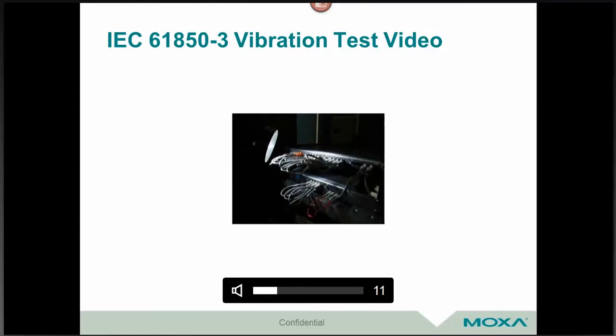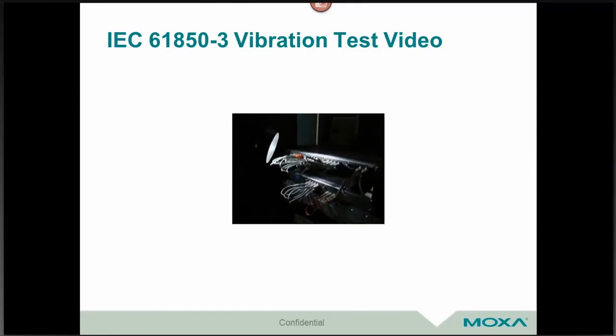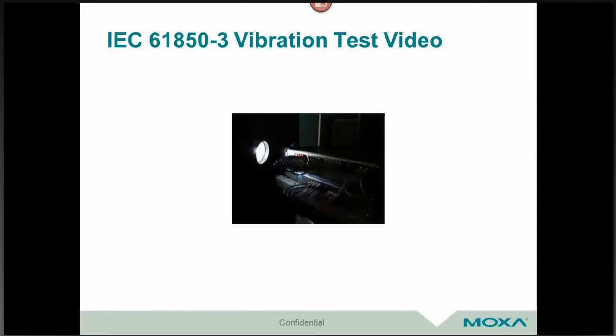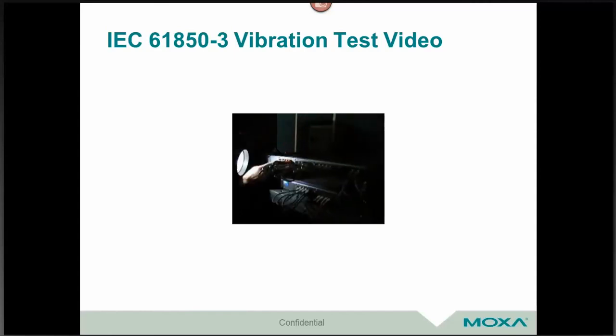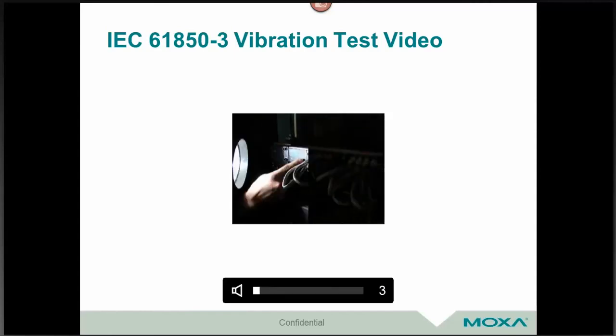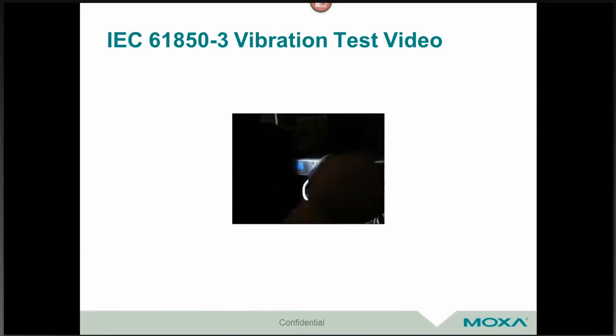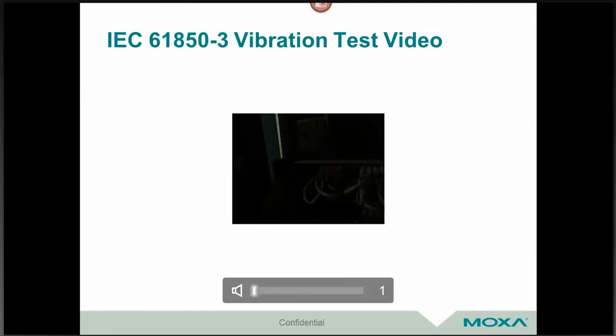This is a video of the actual 61850 switch being tested under 61850 circumstances. It's probably not coming out very well because it is a strobe light, and the strobe light can show you the bending of the chassis and the vibration that you're seeing with the device itself. And it's also showing twisting of the chassis itself and how it is surviving, operating while this test is going on. So chassis going up and down and twisting all at the same time.